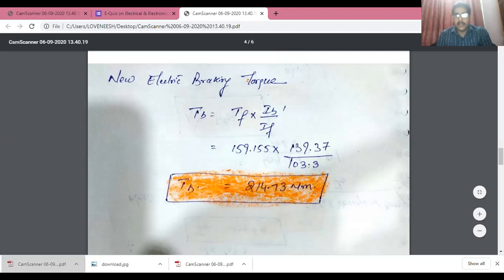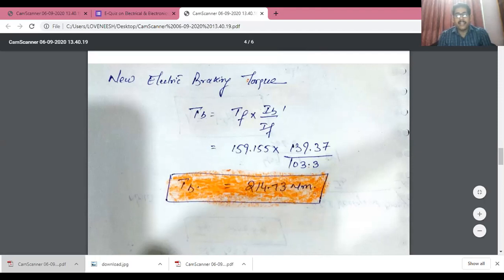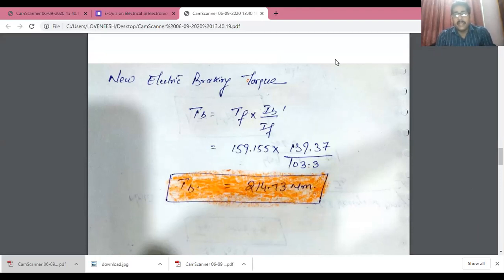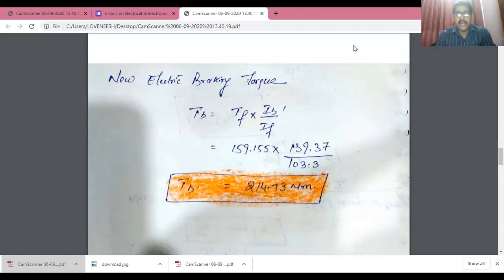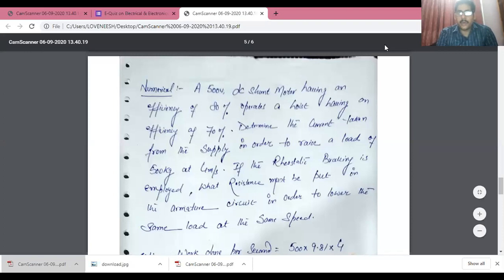So this first numerical is complete. We calculated: (1) the external resistance value to be inserted for plugging, (2) the initial braking current, and (3) the braking torque. One important point to keep in mind: while applying braking, speed decreases from the higher side to the lower side, and simultaneously the back EMF is also reduced — from around 429 volts down to around 69 volts — since speed is directly proportional to back EMF.